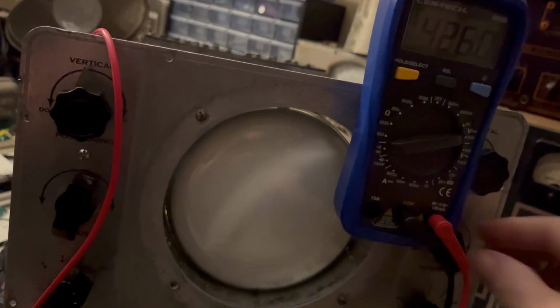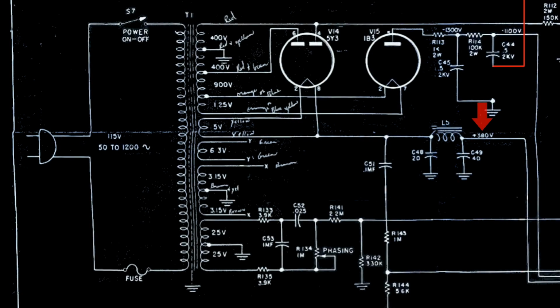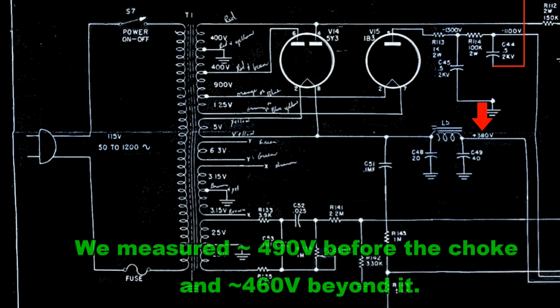Going back to the choke, the reading is 80 volts above what's shown in the schematic, or about 20% above spec. The drawing doesn't indicate what we should expect to see going in, but we know we're seeing a drop of about 30 volts from one side of the filter to the other.